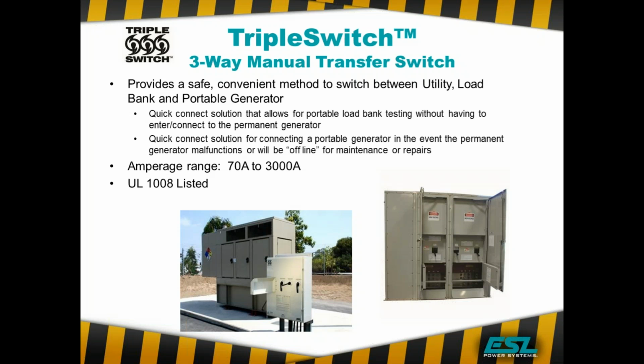70 to 3,000 amps is the range of these units. Again, that means they're UL 1008 listed up to 3,000 amps. That's very unique in the marketplace. Since these are dual purpose, they don't technically fall under UL 1008, because UL 1008 talks only about inlet power, only about having male cams, and these units have both male and female cams. So getting them UL 1008 listed was very cumbersome. We had to go to UL and get all kinds of extra testing done, waivers, everything else, in order to have these UL 1008 listed.